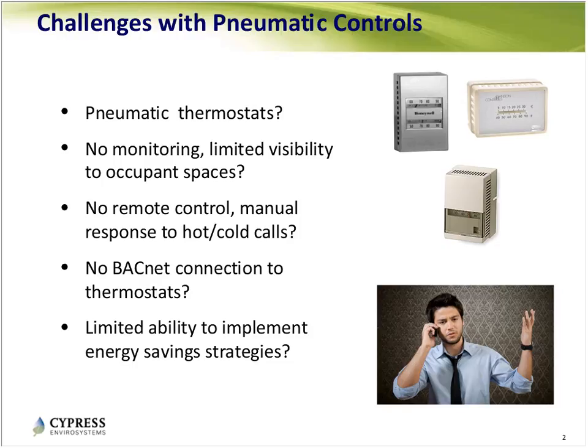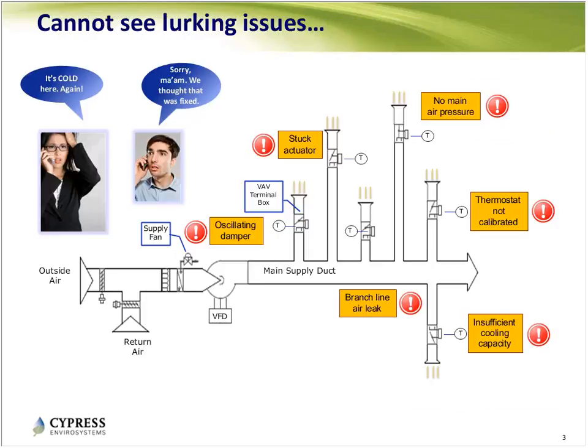Another shortcoming of pneumatics is that you cannot implement a lot of energy saving strategies. I'll talk about that in more detail, but simply put, you cannot do set point enforcement, cannot do deadband set points, cannot do duct static pressure control, cannot do supply air temperature resets. Modern buildings implement many advanced saving strategies, but because of the limited nature of pneumatic controls, you can't do them. That covers the major shortcomings.